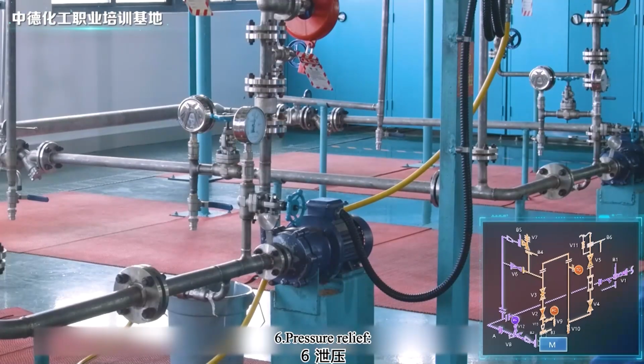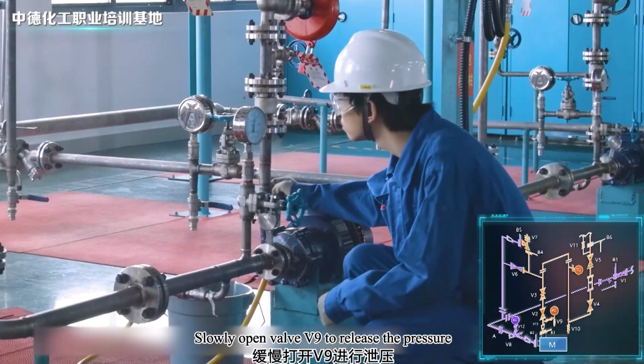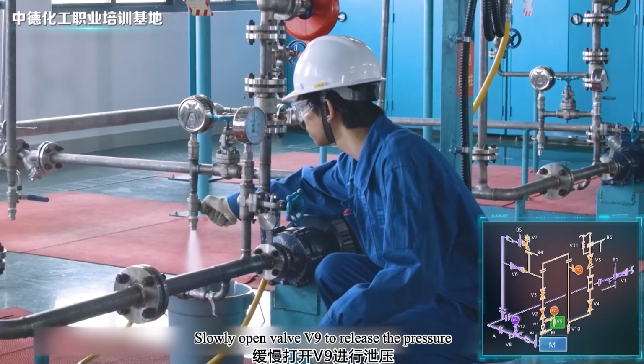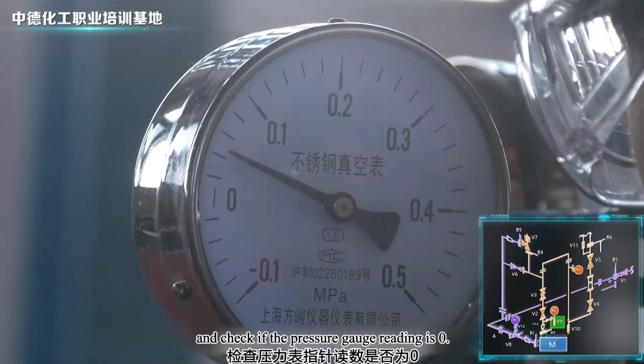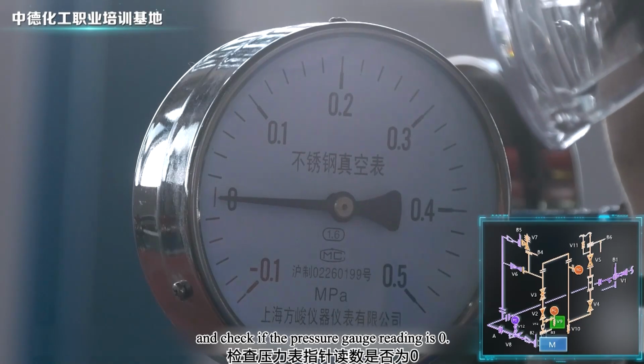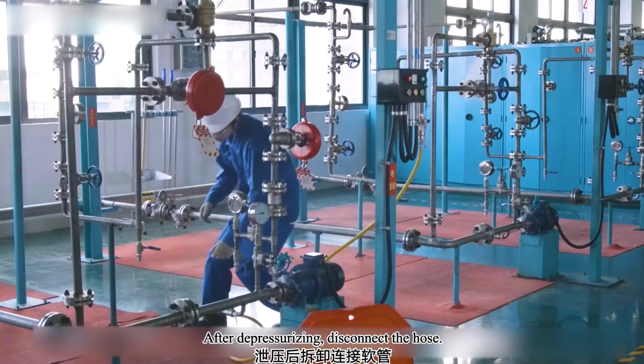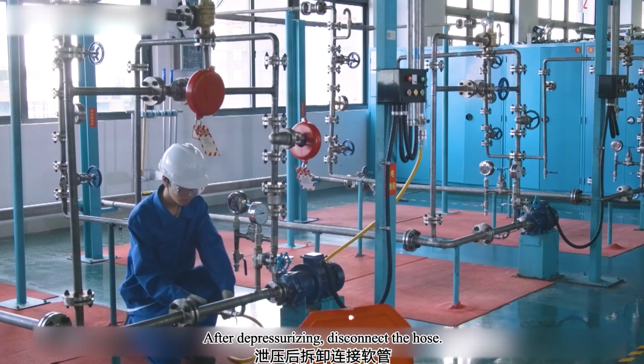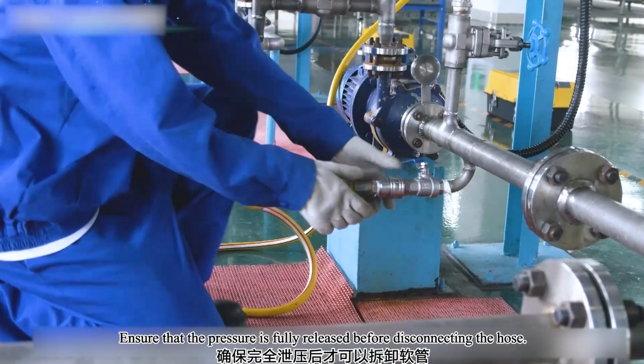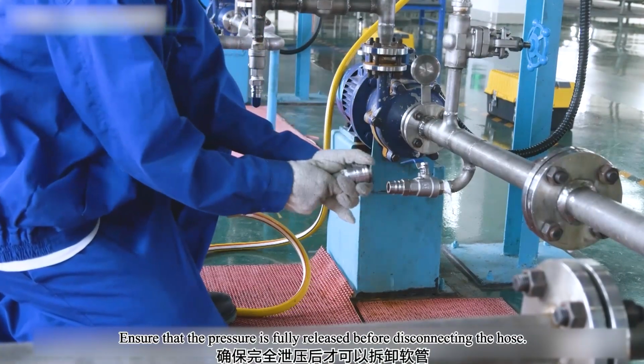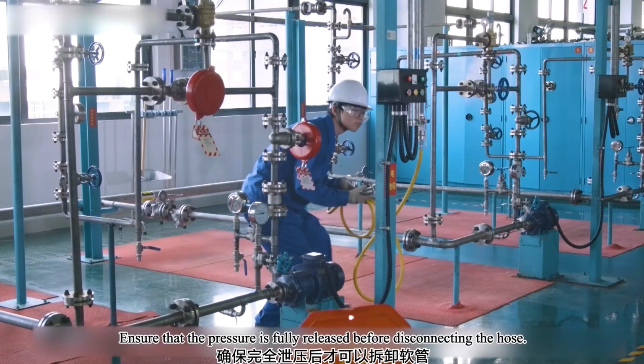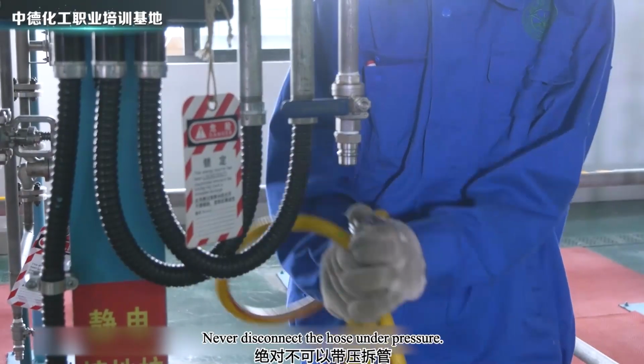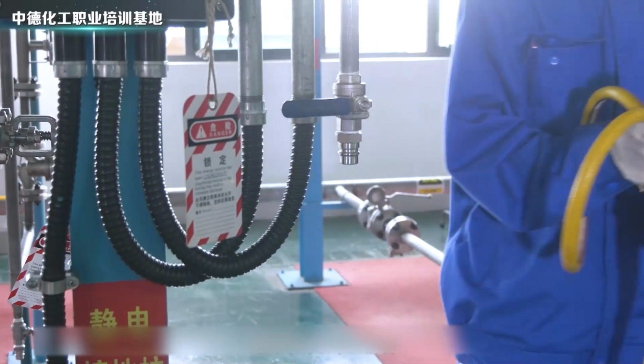Sixth, pressure relief. Slowly open valve V9 to release the pressure, and check if the pressure gauge reading is 0. After depressurizing, disconnect the hose. Ensure that the pressure is fully released before disconnecting the hose. Never disconnect the hose under pressure.